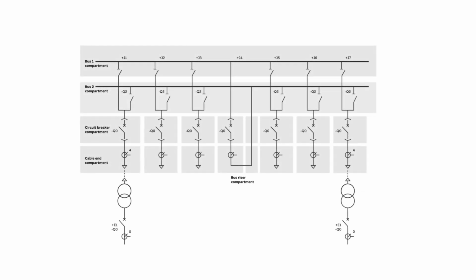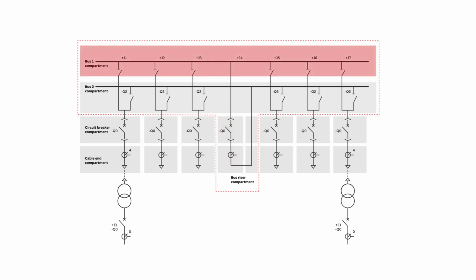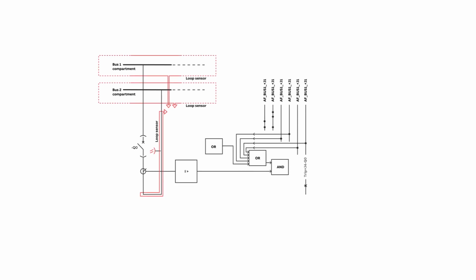As the next step, Matthew considers the bus coupler bay in a similar way. Depending on where the arc fault is, in the circuit breaker, in the bus riser compartment, or in one of the bus bars, the selectivity logic needs to be prepared differently. To accomplish this, there needs to be 3 loop sensors and 1 lens sensor connected to the relay in the bus coupler bay.